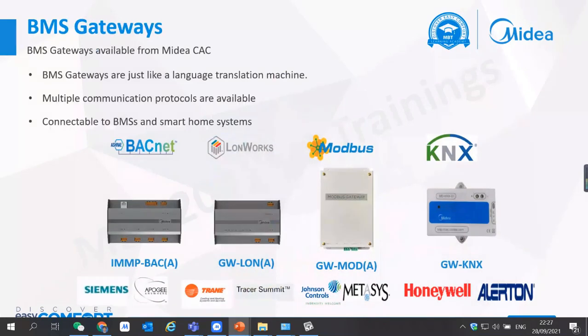We have 4 basic languages for the BMS: BACnet, LonWorks, Modbus, and KNX. We have gateways available for all 4 languages, with different capacities. It has 4 ports, each port supporting 8 systems and 64 indoor units, or 8 systems and 32 indoor units, or 8 systems and 64 indoor units, and this one connects with each IDU D1, D2 port.